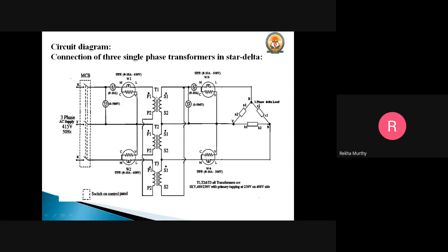Here you can see the same observation. P1 is let out to the R phase, P1 of the second transformer is let out to the Y phase, and P1 of the third transformer is let out to the B phase. Now the remaining P2 of first, second, and third transformer, all these P2 should be shorted together.